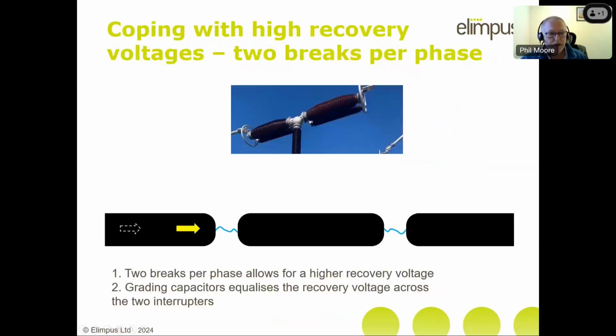And one of the things, and this is very, very common at all 400 kV breakers, is that you would have two sets of contacts or two sets of interrupters in series. So you can see there's one set here and there's another set there. So what you're really doing is dividing out the transient recovery voltage across the two gaps, which allows the breaker a greater chance of breaking the arc and ensuring that it doesn't come back.